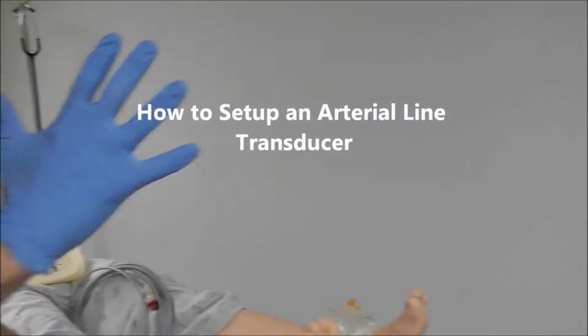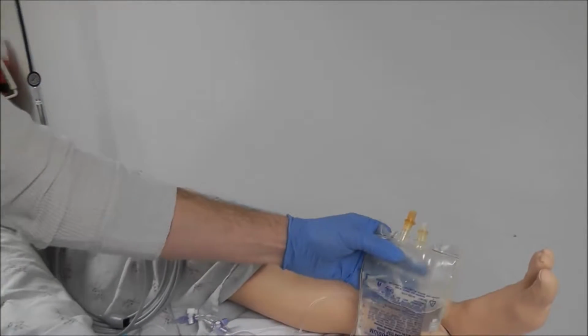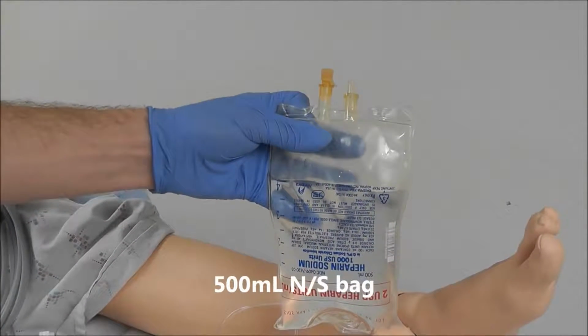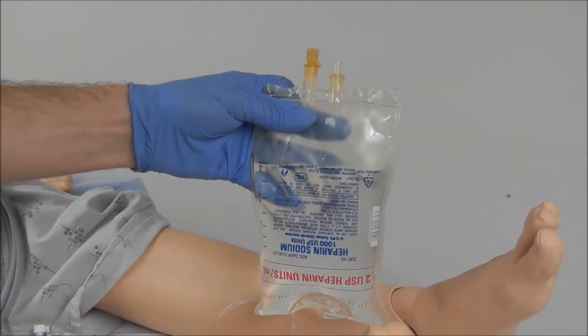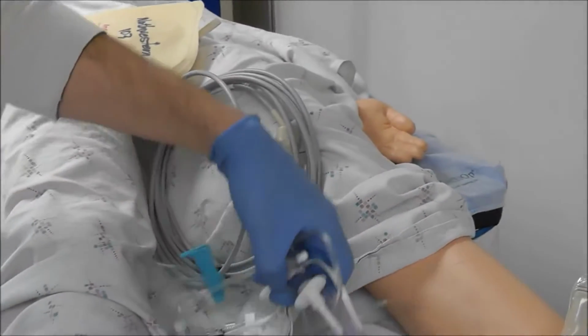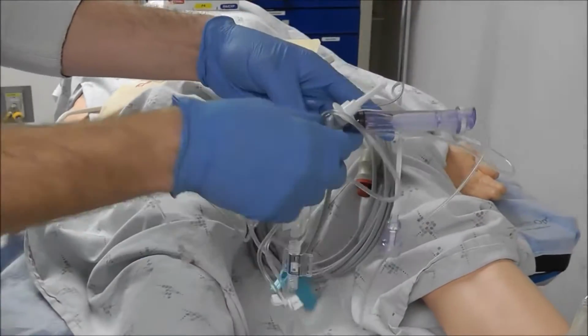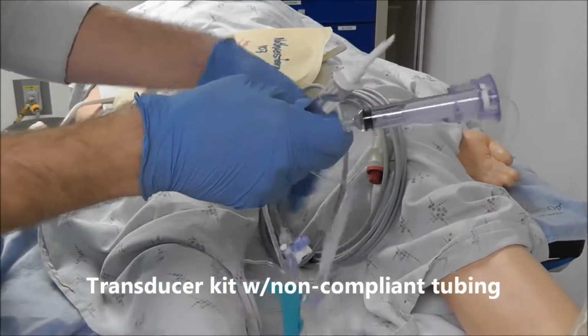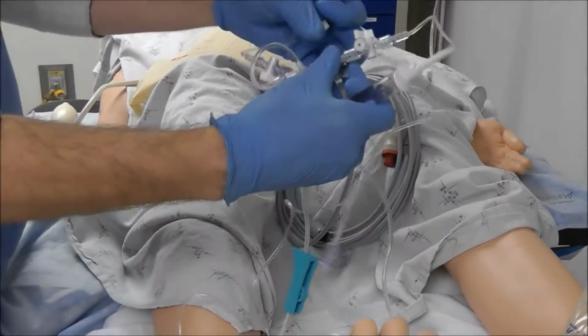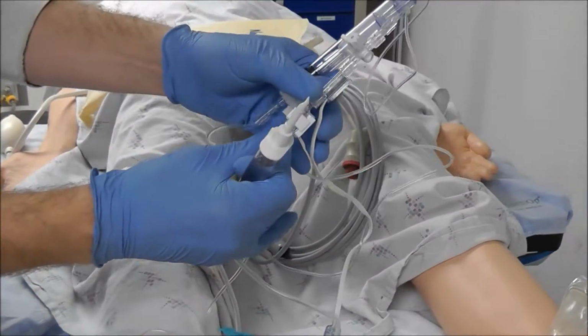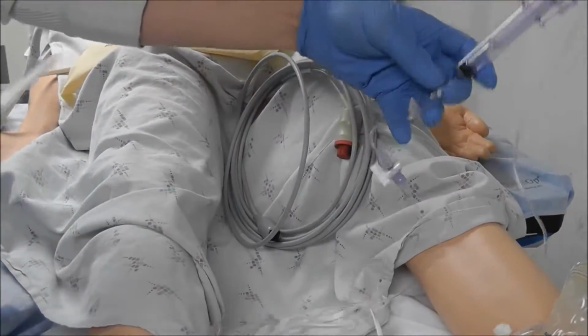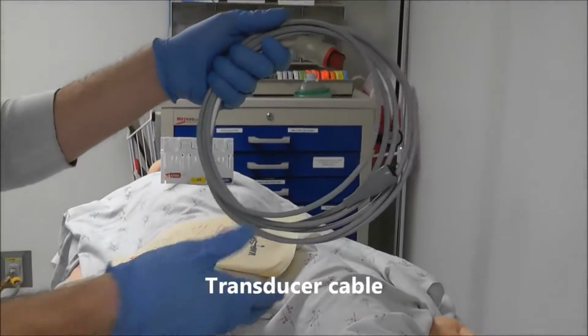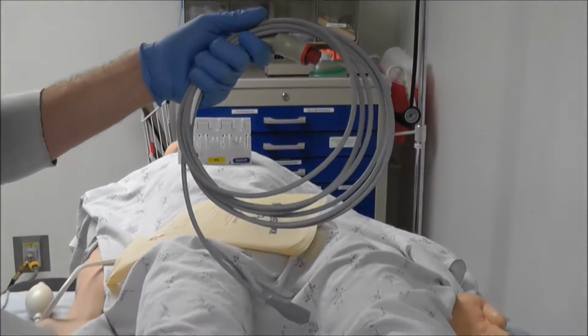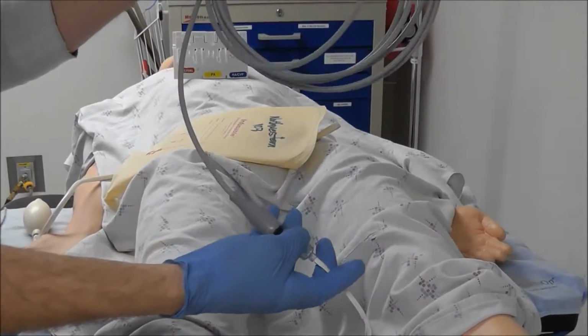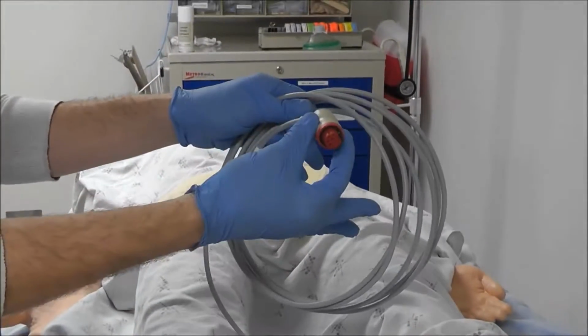We're going to need five things when we're setting up an arterial line, okay? Number one is you're going to need a 500 cc bag of saline or heparinized saline. The next thing that you're going to need in setting up an arterial line is you're going to need the actual transducer that is connected to non-compliant tubing, okay? So that's number two. Number three is you're going to actually need a transducer cable, because we're going to want to be able to hook this transducer tubing here up to our monitor there.